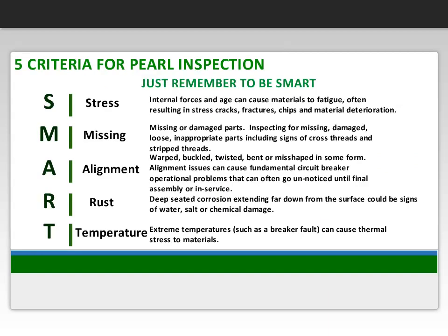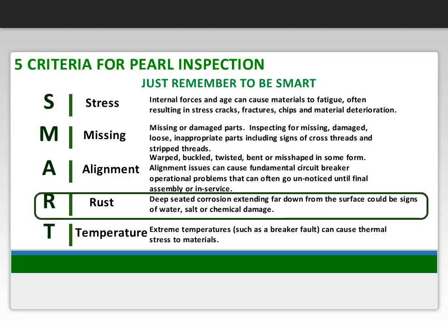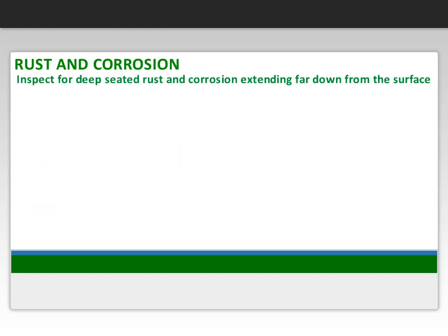The fourth inspection criteria you'll frequently find throughout the Pearl inspection standards is inspect for rust and corrosion. Deep-seated rust and corrosion extended far down from the surface could be signs of water, salt, or chemical damage. If you're going to perform a complete rebuild of a unit, most surface rust can be removed during the cleaning process. But if you're just doing an inspection and test, the unit needs to be rust and corrosion free. Rust on non-electrical parts like enclosures does not always prevent proper operation. Many plants have moisture in the air that cause surface rust.